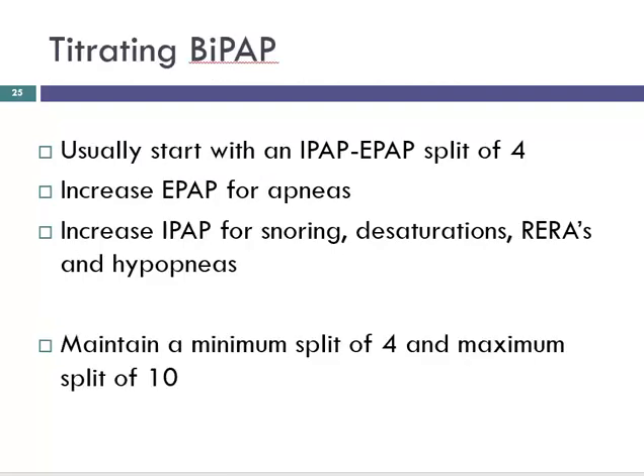So how we do the titration, where CPAP is fairly simple, it's one pressure. You kind of keep turning it up slowly until you eliminate the respiratory events. BiPAP is 2 pressures, so it's a more complex titration. We need that pressure split of at least 4, and you can't go higher than 10. You can't have more than a 10 pressure difference between your inspiratory and expiratory, which means, say EPAP is at 10, IPAP can be anywhere between 14 and 20. Make sense?